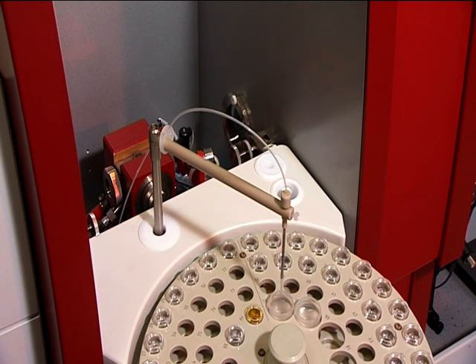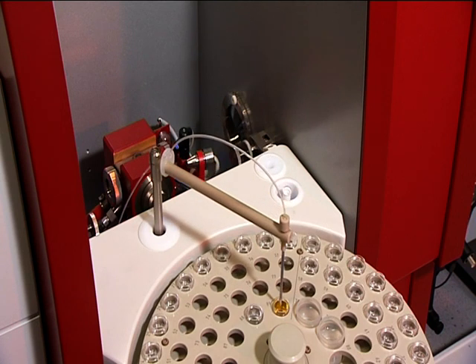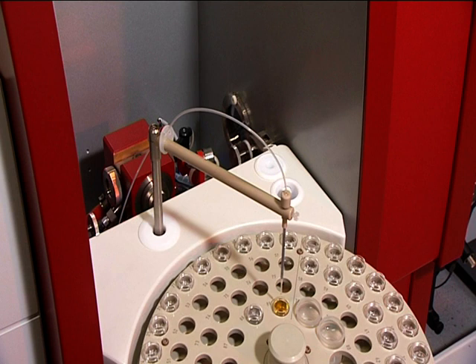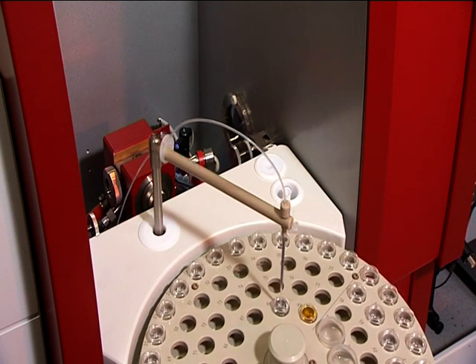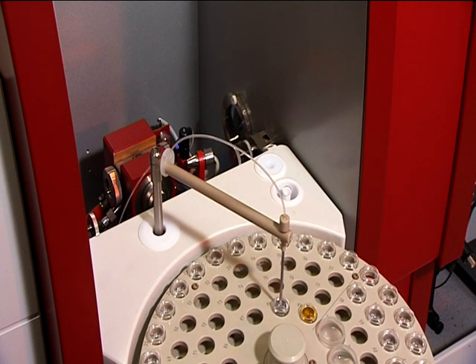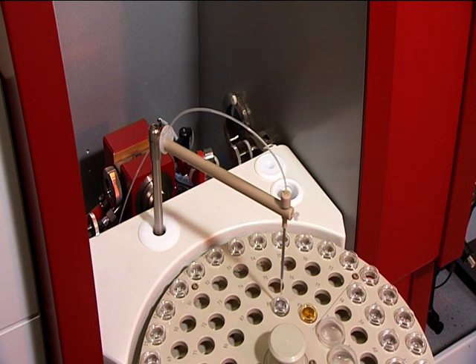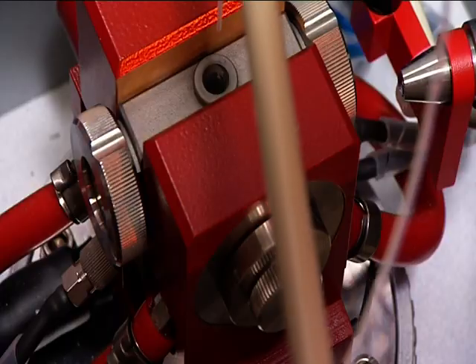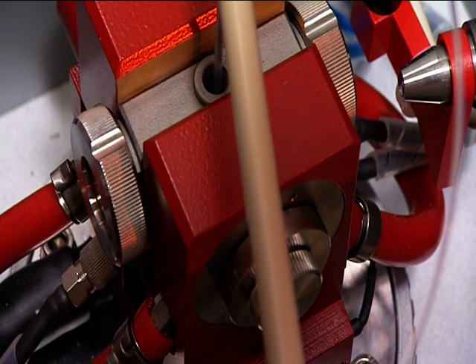The micropipetting unit takes over the complete handling of samples, standards and modifiers. Aside from preparing calibration standards by diluting an automatic addition or modifier, samples can be diluted or concentrated in the graphite furnace as necessary. The turntable with 89 positions makes automated measurement of large sample series possible.